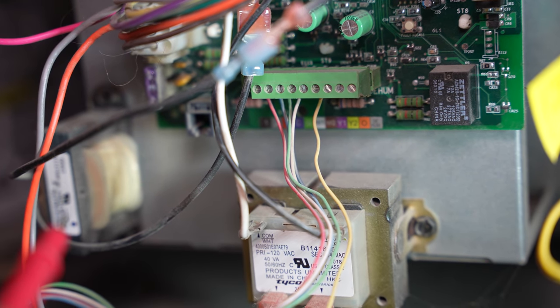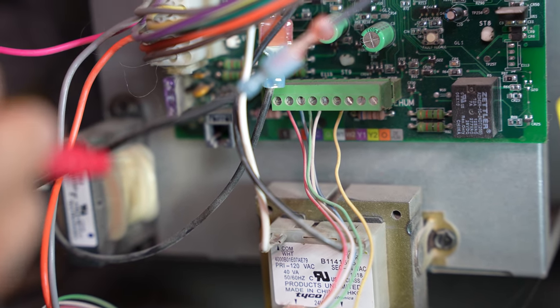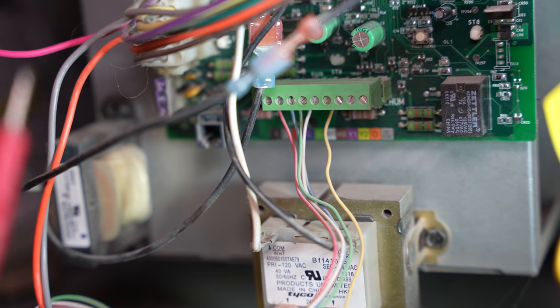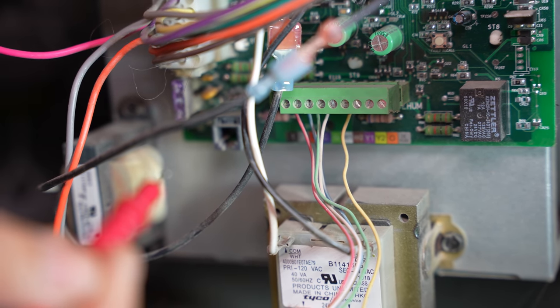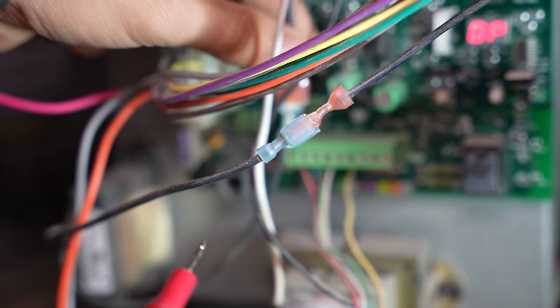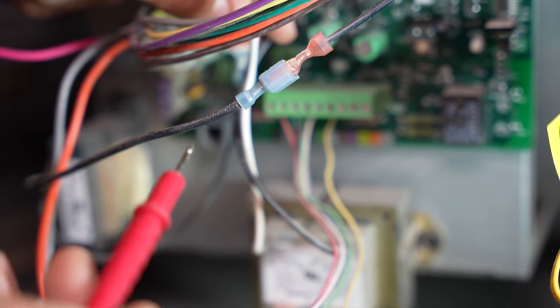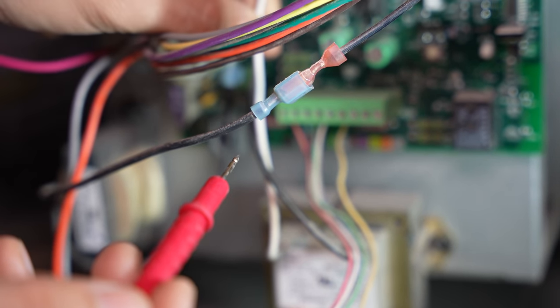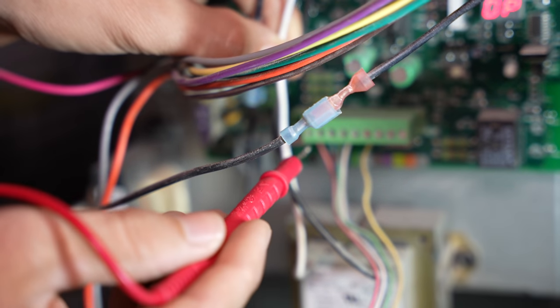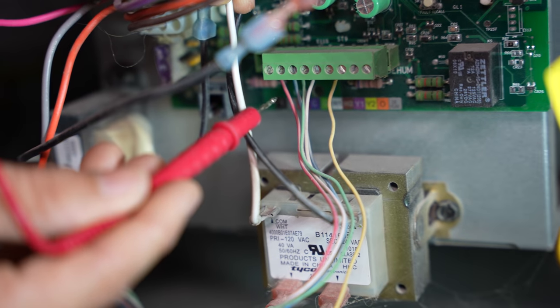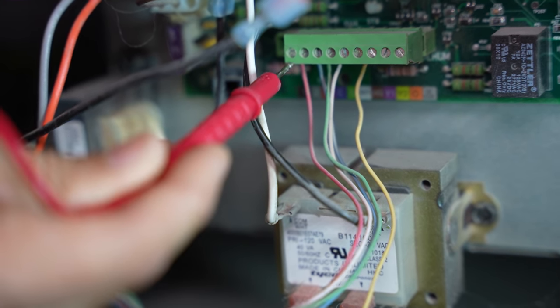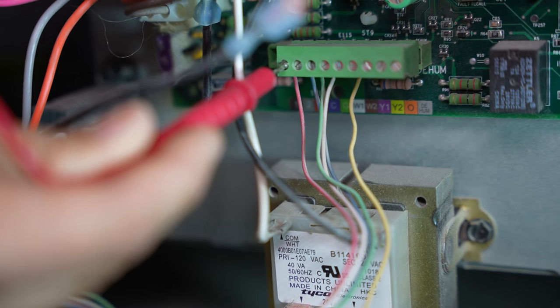And one last thing I would like to mention is that if you're looking for that 24 volt common because you're troubleshooting with a meter, instead of the 24 volt common, if for some reason you absolutely can't find it, you could just use ground or the chassis, the body of the furnace. So for example, if I put one meter lead on R, that's where the red wire is going. If I put one meter lead on R, that's going to be our hot.